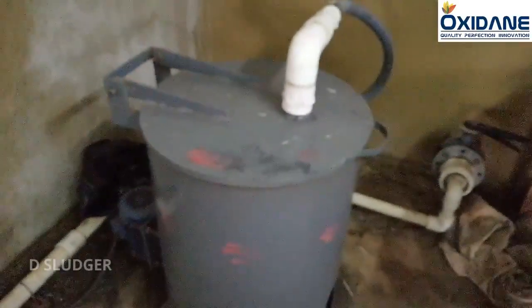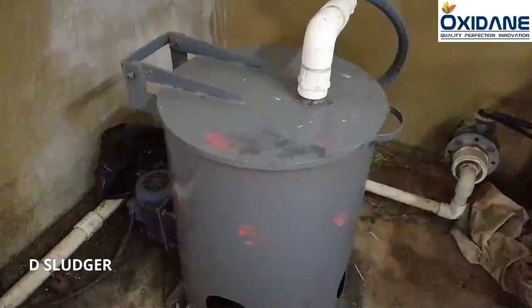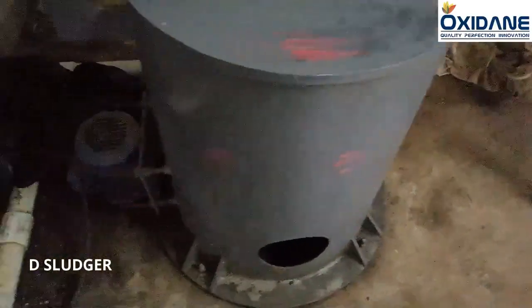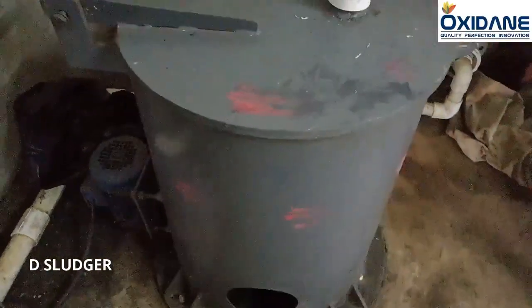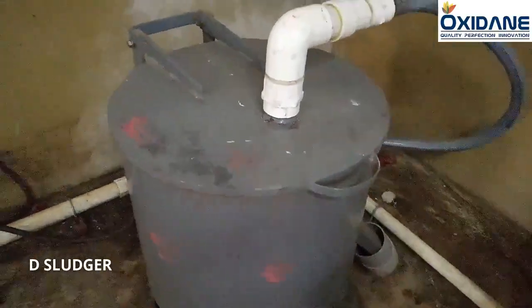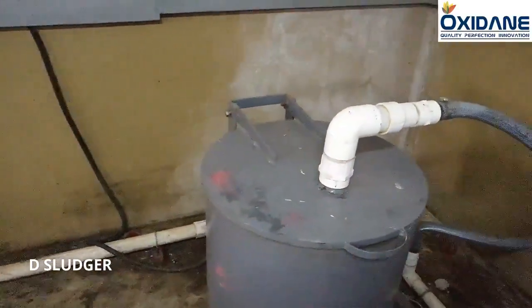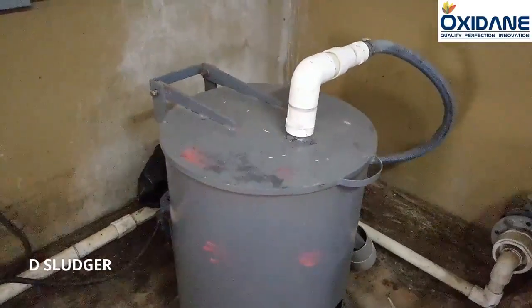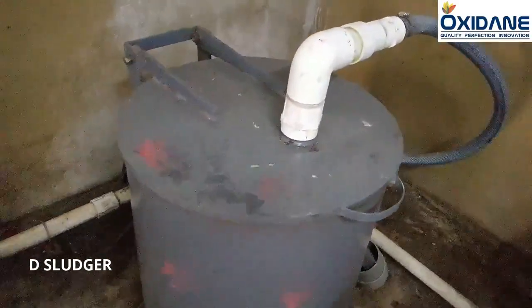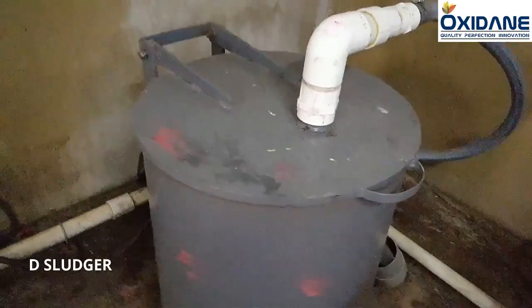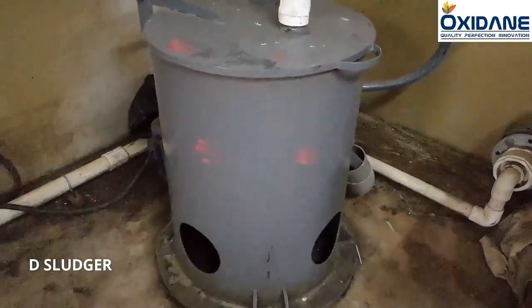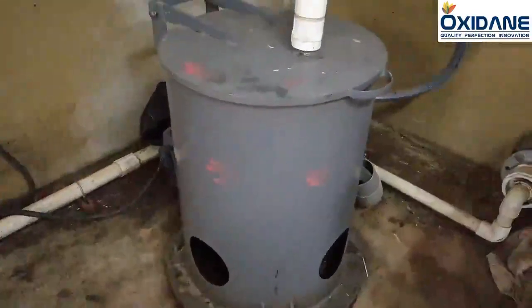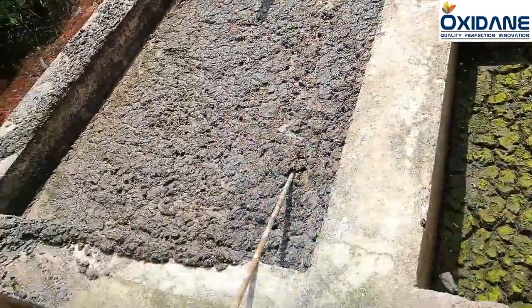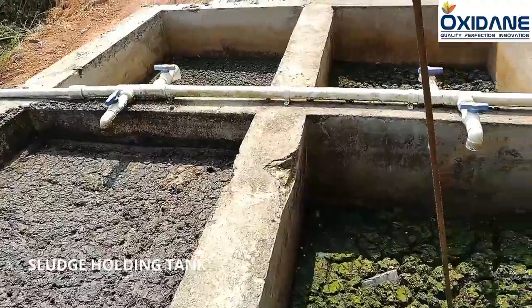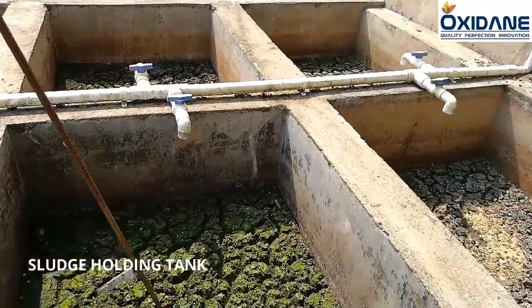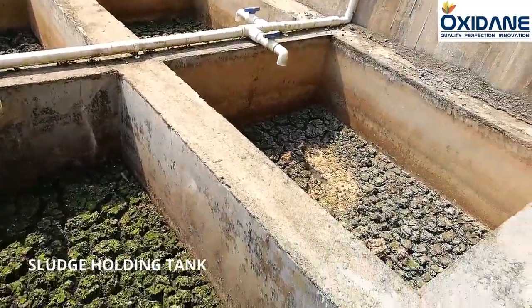Centrifugal desludger is used in the process which uses the force developed by fast rotation of a cylindrical drum or bowl to separate the sludge solids from the liquid. In the basic process, when a sludge slurry is introduced to the centrifuge, it is forced against the bowl's interior walls, forming a pool of liquid. Density differences cause the sludge solids and the liquid to separate into two distinct layers. The sludge solids cake and the liquid centrate are then separately discharged from the unit. The excess sludge is sent to sludge holding tank to be disposed of.